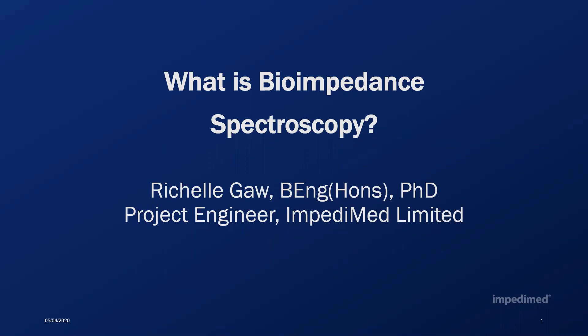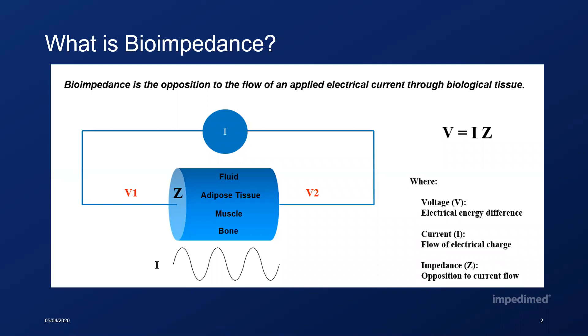So what is bioimpedance? In simplest terms, bioimpedance is the opposition to the flow of an applied electrical current through biological tissue. But what does this actually mean and how do we measure it? We use a device that generates an input current that is imperceptible to humans. The current is the flow of electrical charge, and this charge is injected into the body through a first set of drive electrodes and will always follow the path of least resistance.